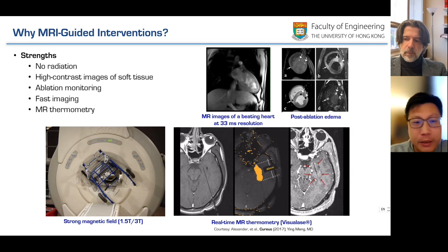But the downside is that MRI has to generate a very strong static magnetic field, typically 1.5 to 3 tesla. Only 1.5 tesla is already sufficient to suck a wheelchair or hospital bed back into the donut. If you search the keyword MRI accident, you'll find a lot of similar pictures of people misusing the MRI system. That could be very dangerous if there's a patient inside the iso-center, inside the donut.